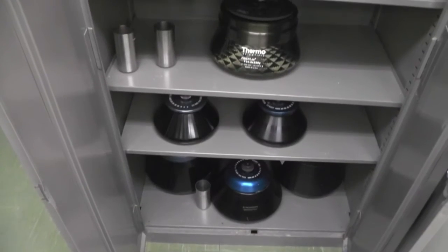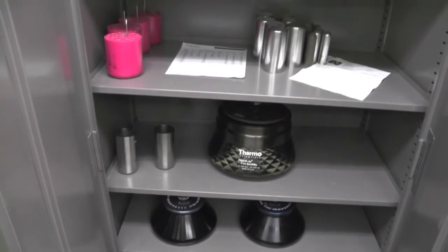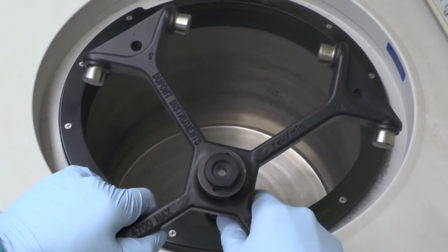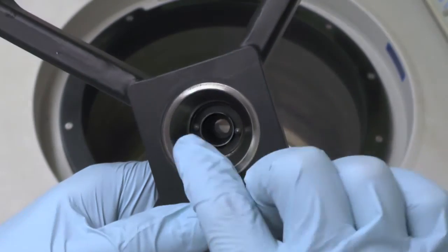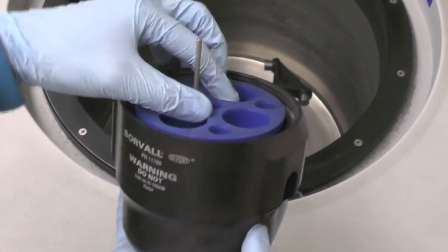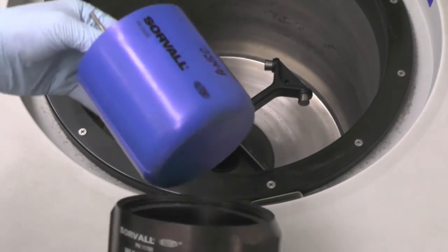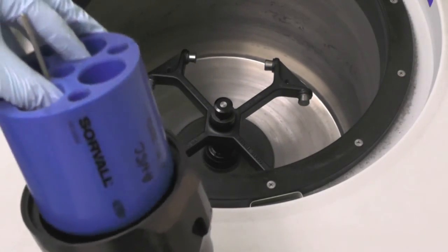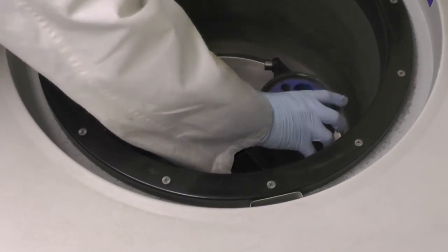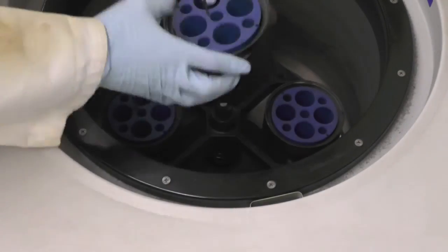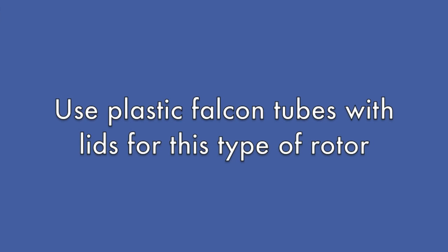There are many types of rotors in the cabinet beside the centrifuge. Another rotor frequently used in the lab is the Sorvall SH-3000 rotor. Again, position the rotor so the pins do not overlap. Tighten the screw to secure the rotor. Place the tube holder onto the rotor by fitting the slots, which is on the tube holder, onto the hinges on the rotor. Place all 4 tube holders on, and you should use plastic Falcon tubes with screw lids for this type of rotor.